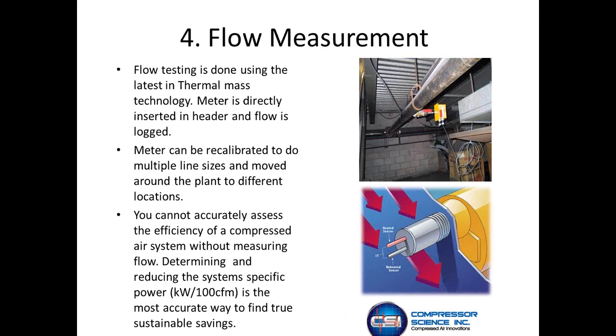Flow measurement: I've gone through several different types of flow meters over 15 years and found thermal mass to be the most accurate when it comes to compressed air. It's inserted directly into the distribution header. We can either do a hot tap or we drill a saddle, a Victaulic type saddle, into the header. There's no access downstream of air treatment equipment. We can recalibrate this meter for different line sizes, so we can take the meters into other areas of the plant and measure specific processes if we're looking at energy savings by shutting off processes or relegating specific compressors to a process.